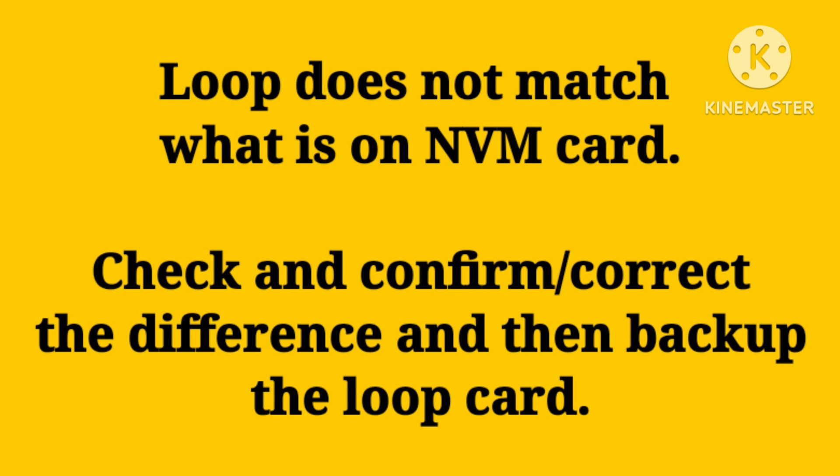Check and confirm or correct the difference, then back up the loop card. The troubleshooting for this fault is simply to back up the loop card, and it will be resolved. Also, if you get a 'loop stopped at card X' fault, it means that previous data was lost — possibly a cable or something on that part of the loop is bad.